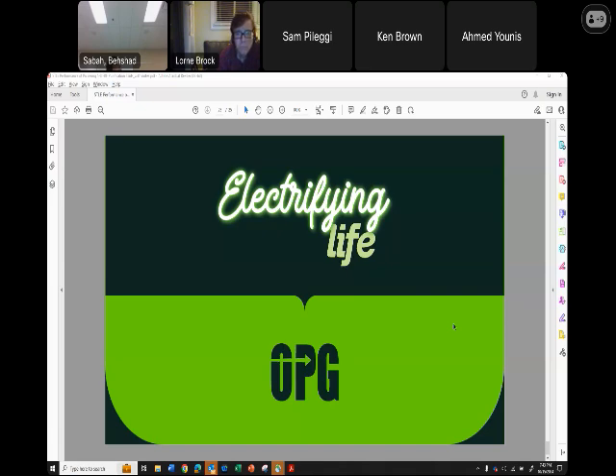So what I normally recommend is just keep the MPC as low as possible. I think trying to get it to a 15 or less is not the right goal when there's secondary or more complicated factors going on in the system. For MPC removal, we want to see in mineral oils one time exchange per day in the tank. In synthetic oils or in areas where there's some more severe stress, we try to increase that to 3 times per day cycle time. Okay?